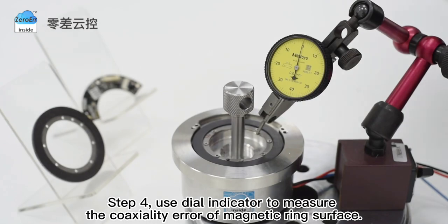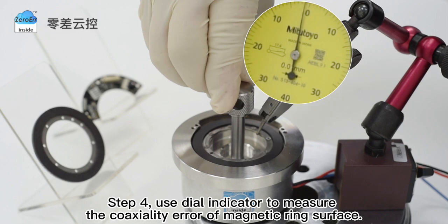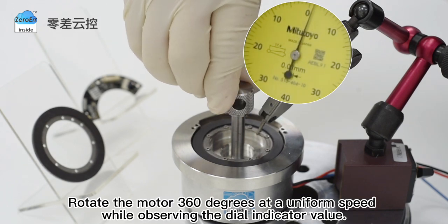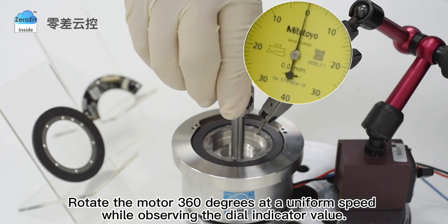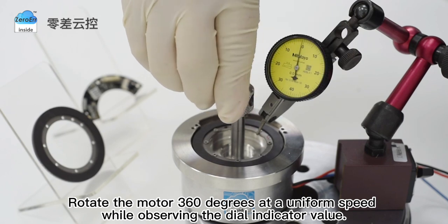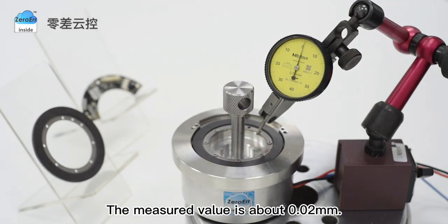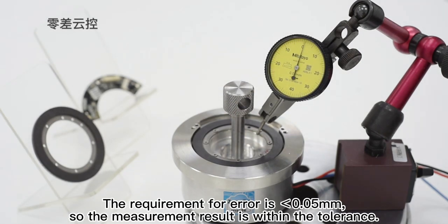Step 4, use dial indicator to measure the coaxiality error of magnetic ring surface. Rotate the motor 360 degrees at a uniform speed while observing the dial indicator value. The measured value is about 0.02 mm. The requirement for error is less than 0.05 mm, so the measurement result is within the tolerance.